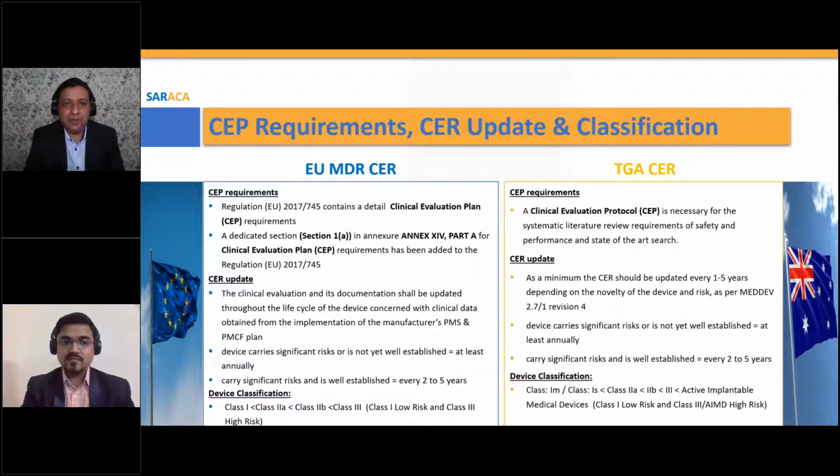Another very important point, and a question we always ask our customers, is about CER update. When do we really update our CER? There is no very clear guideline. Obviously, you have boundaries, but the best assessment is with you. As Sam pointed out, risk is always a critical thing in medical device development. You have to assess the risk of your device, and if you see it's on the higher side, it's always better to update faster.